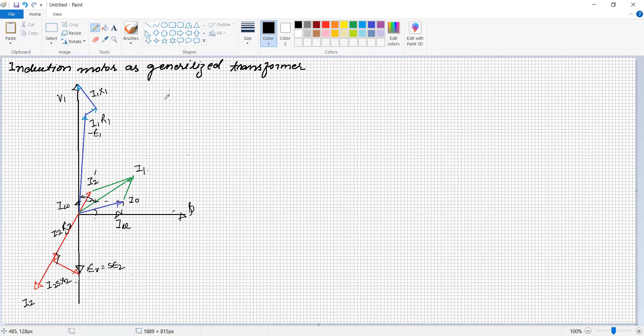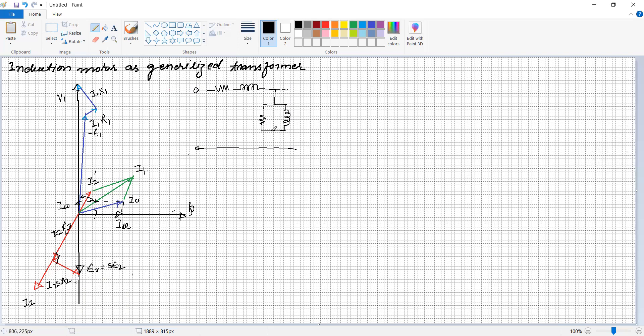Under such conditions, we can draw an equivalent circuit of the stator winding with resistance R1, reactance X1, and an exciting shunt component. The current in the stator winding is I1, and the no-load current is I0, which has two components: magnetizing component Imu and core loss component Iw.